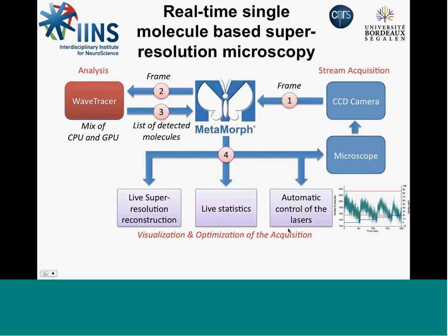Because, as I introduced before, you need to have molecules which are sparse enough, one from the other, so that you can localize them. If it's too dense, you will not be able to localize precisely, and it will lead to errors. But if you have too low a density, then the acquisition time for all the molecules will be much longer than the ideal one. So the automatic feedback allows you to put limits and say, if you go below or above this threshold of intensity, please adjust the laser automatically. There is an activation laser which allows you to give it more or fewer molecules.